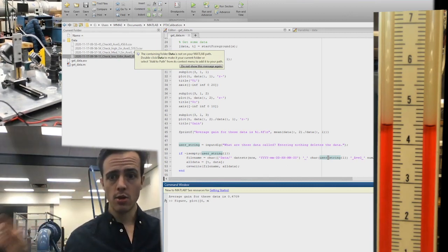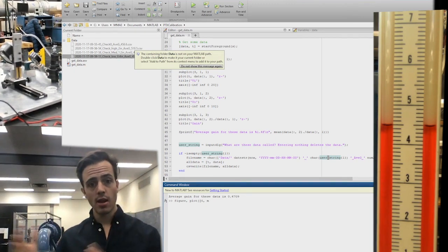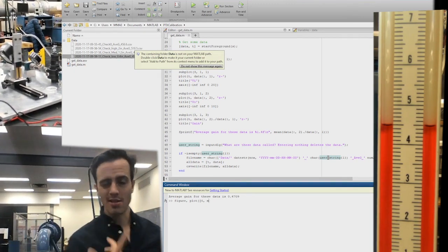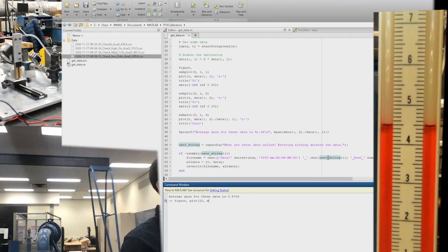Obviously, for the actual calibration, you guys are plotting delta P, but since delta H is linearly proportional to delta P, I can just plot these, and this will show me whether I've got linearity in my transducer or not. So 0, 0.4, 1.2, and 2, and those data correspond to certain gains.